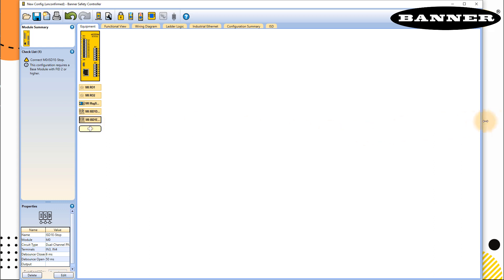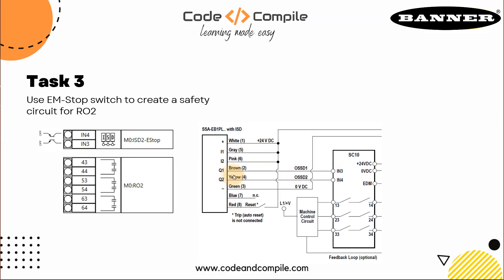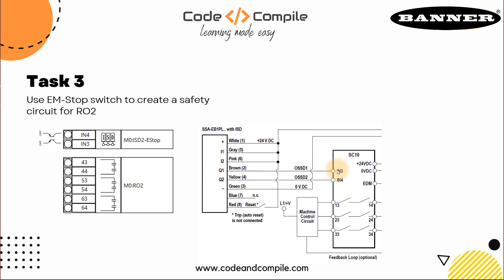All you have to do now is make a circuit for RO2. If you want to see the wiring of E stop, this E stop is connected to IN3 and IN4. For this example, it gets 24 volts to the white wire, gray wire, and pink wire all connected to 24 volts. It's also connected to a reset button, which is optional. You have zero volt connected to wire green, and these are the two outputs q1 and q2 going to IN3 and IN4.